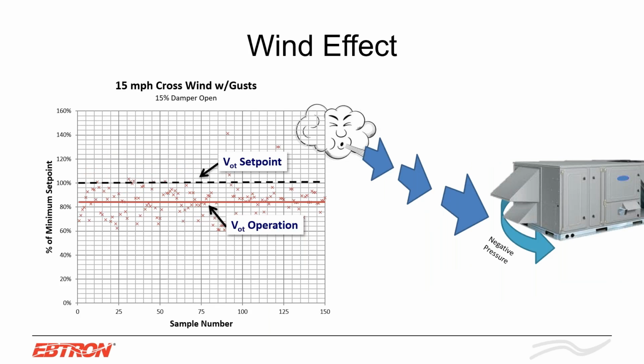Well, let's take this a little step further, right? It's Monday morning. Again, the balancer set this up on a Friday. Now it's Monday morning. Your system goes into morning warm-up. Well, now you have a 15-mile-per-hour crosswind going across the intake of this unit right here. What does that do? That creates a negative pressure drop. So when you thought you were bringing in 100% of the setpoint, now you're under-ventilating by 20%, and you're not complying with whatever code or standard you're designing to.